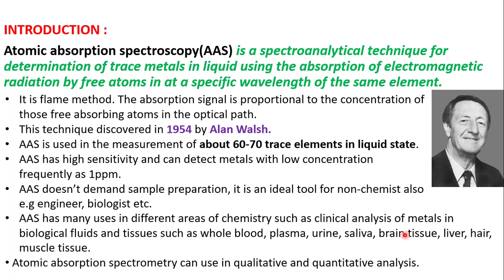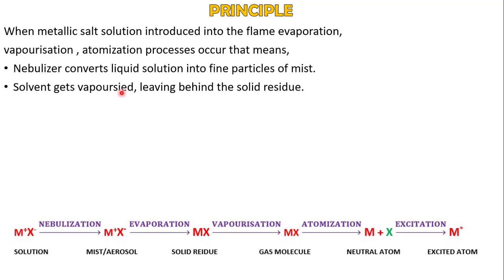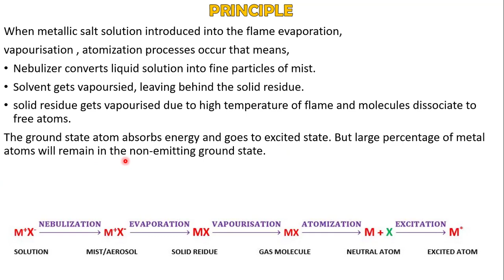Principle of atomic absorption spectroscopy. When a metallic salt solution is introduced into the flame, evaporation, vaporization, and atomization processes occur. That means the nebulizer converts the liquid solution into fine particles of mist or aerosol. Then the solvent gets vaporized, leaving behind the solid residue. The solid residue gets vaporized due to the high temperature of the flame and molecules dissociate to free atoms. The ground state atoms absorb energy and go to an excited state. But a large percentage of metal atoms will remain in the non-emitting ground state.